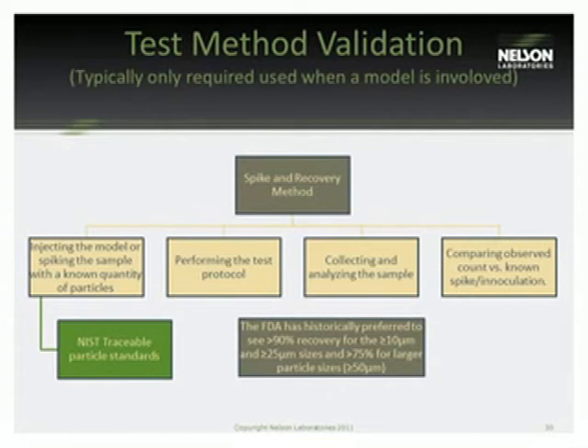And the purpose of this, as described earlier, is to make sure that the particulate matter that's generated during the test is sufficiently removed and extracted from any accessories and models that are used so that they may be analyzed on the particle counter or microscopically. In any cases where particulate matter is harbored in these, it's essentially the same as the particulate matter being harbored in the bloodstream, which isn't really accurate if you're only getting, say, a 50% recovery in your test and showing rather low numbers, but in truth, twice that amount of particulate is going to be subjected to the patient.